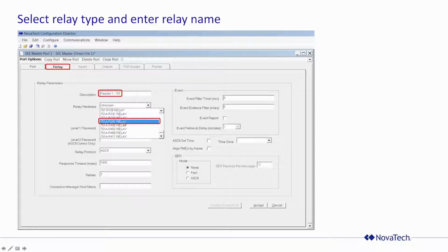If the file doesn't exist, we create a brand new one for you right there in the substation. It stores it back into the defaults, so you don't have to call us to develop a new pick list — it does it for you automatically. That only works with Schweitzer ASCII or fast messaging, not DNP pick lists, not Modbus, just fast messaging. Okay, I've selected my relay.